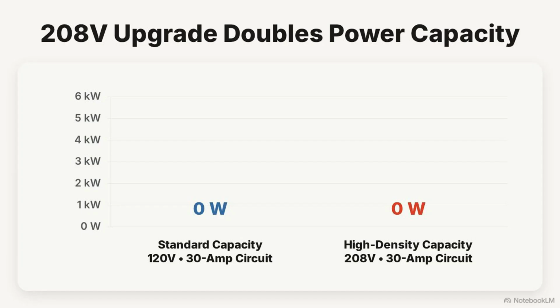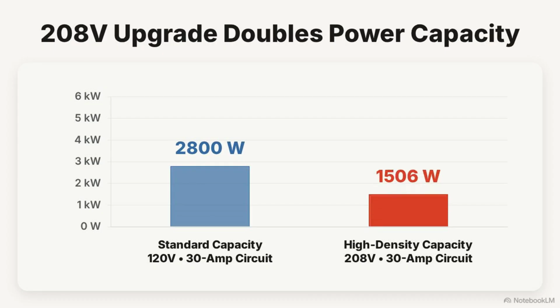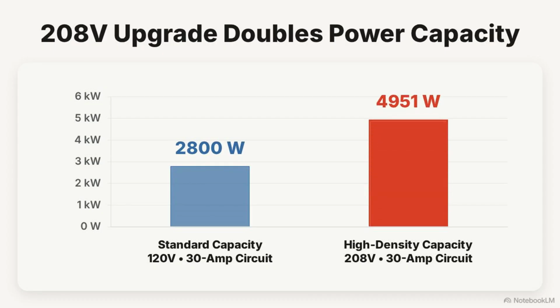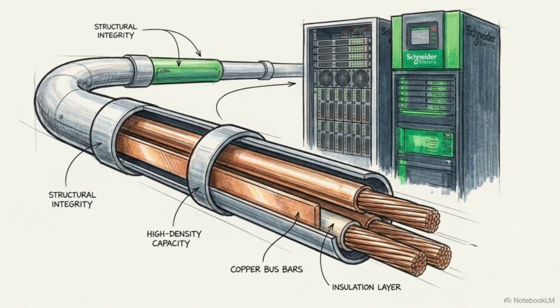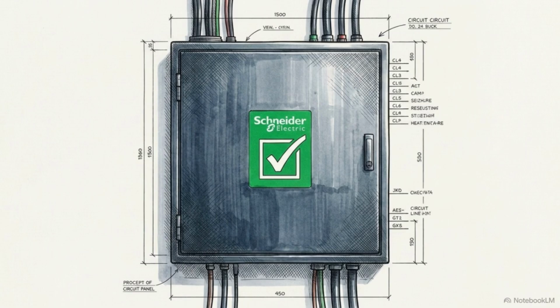Upgrading wall receptacles to native 208-volt power changes the math. As you can see, the same 30-amp circuit delivers 2.8 kilowatts at 120 volts, but 5.0 kilowatts at 208 volts. Phasing out transformers and switching to 208 volts doubles your usable compute capacity on the same physical copper wiring. This allows you to scale density without expensive electrical panel overhauls.